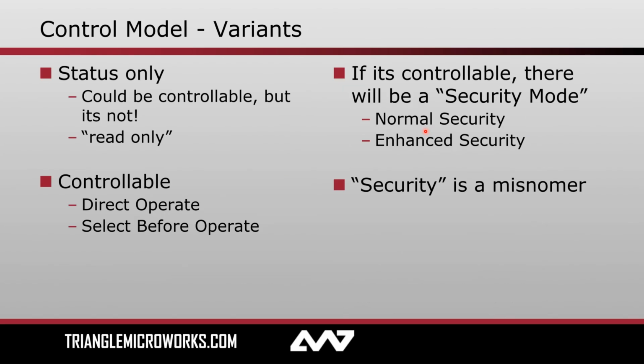So first, let's talk about the different variants. Well, first, this isn't much of a variant, status only. If you see status only on a control, that means that it has not been configured to be controllable. It could be controllable, but it's effectively in a read-only mode, and you as a client cannot actually control it. But let's assume it is configured for control.